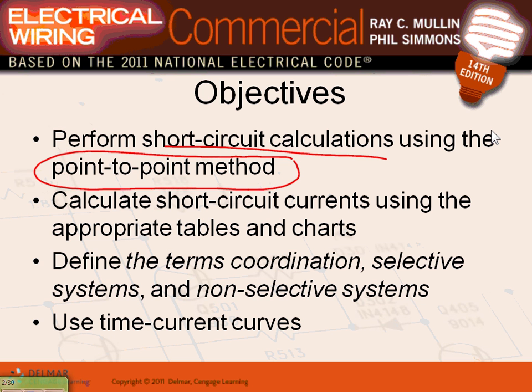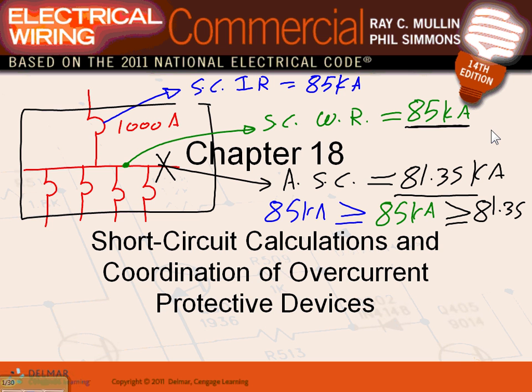And the whole idea of short circuit calculation, Ashley, is to come up with this value. How am I going to come up with this value? That's what you're looking for. Because based on this value, the 81.35, I can size the withstand for my equipment and the interrupting for my circuit breakers. So you always start with the available short circuit. How am I going to calculate the available short circuit? Can you guys follow me? Yep, Chad. The available short circuit is your start point.